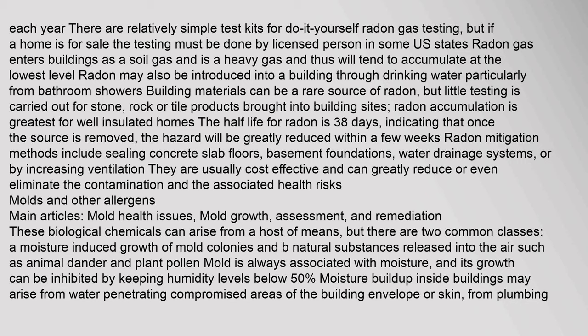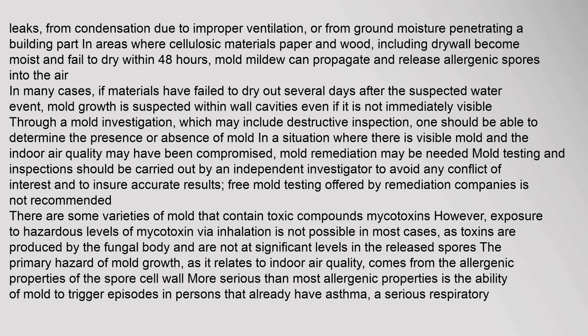Moisture buildup inside buildings may arise from water penetrating compromised areas of the building envelope or skin, from plumbing leaks, from condensation due to improper ventilation, or from ground moisture penetrating a building. In areas where cellulosic materials — paper and wood, including drywall — become moist and fail to dry within 48 hours, mold and mildew can propagate and release allergenic spores into the air.